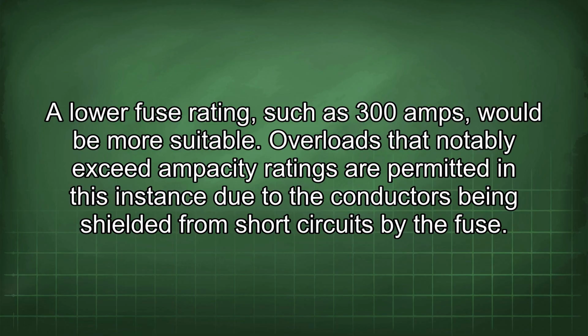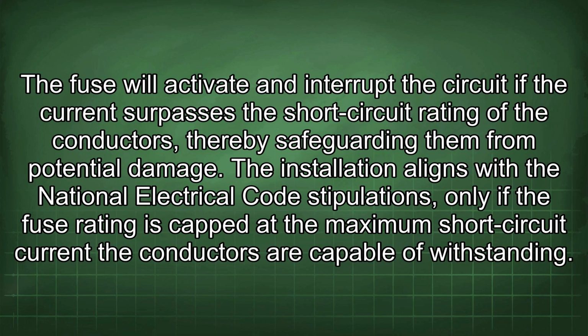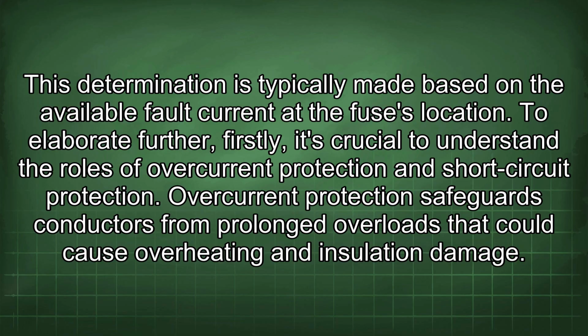Overloads that notably exceed ampacity ratings are permitted in this instance due to the conductors being shielded from short circuits by the fuse. The fuse will activate and interrupt the circuit if the current surpasses the short circuit rating of the conductors, thereby safeguarding them from potential damage. The installation aligns with the National Electrical Code stipulations only if the fuse rating is capped at the maximum short-circuit current the conductors are capable of withstanding. This determination is typically made based on the available fault current at the fuse's location.